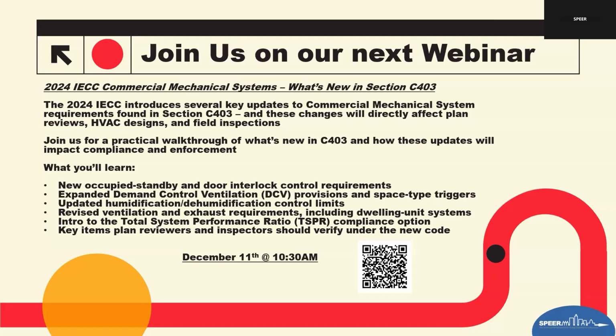Demand controlled ventilation, which was introduced in 21, has now been expanded with more provisions and space type triggers. There's an updated humidification, dehumidification control limit, especially for horticulture areas. Then there's revised ventilation and exhaust requirements, including dwelling unit systems. There's now a new total system performance ratio, TSPR, compliance option, which may gain some popularity depending on whether everyone can understand how that's being done. And then, of course, key items in plan review and inspectors should verify when the new code comes out.